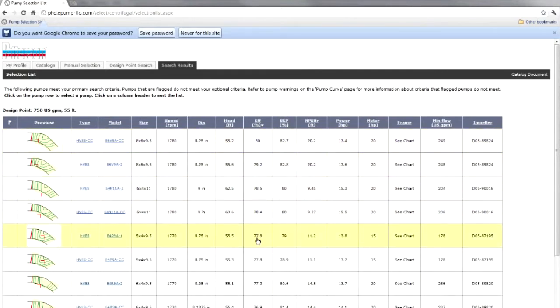Notice that I'm now dealing with a 5x4, 5-inch suction by 4-inch discharge, and the pump up above is an 8-inch suction and a 6-inch discharge. The larger your pumps go, the better your efficiencies can be. The question is, should I go with the closed coupled or should I go with the flex coupled?